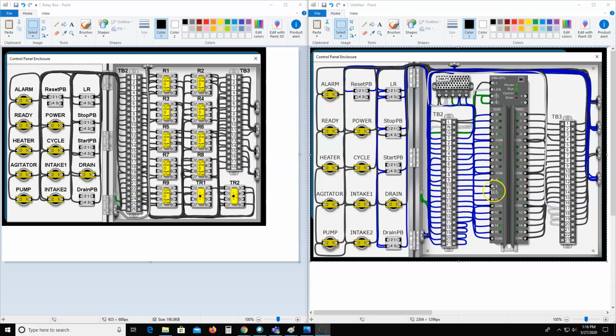So that's why we use PLCs over relay logic, because these guys may be $12, $15, $20 a piece depending on what type of relay, but you've got 11 in total. You start adding up the cost of that and the time it takes to do that, not to mention relays are mechanical devices, and even though this may use some relay type things in here, these things have a higher failure rate a lot of times than PLCs do as far as inputs and outputs.